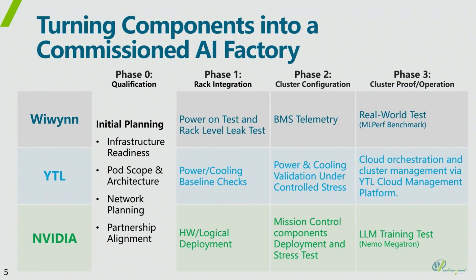Based on NVIDIA's suggestion, once we finish the qualification jobs, we can move to phase 1. Phase 1 means the real rack, the GB200 rack, is manufactured and validated at the L11 level in Wiwynn's factory in Malaysia. After the L11 testing is finished, we move those racks into YTL's data center and test again, including configuration and fabric networking installation, then test again.